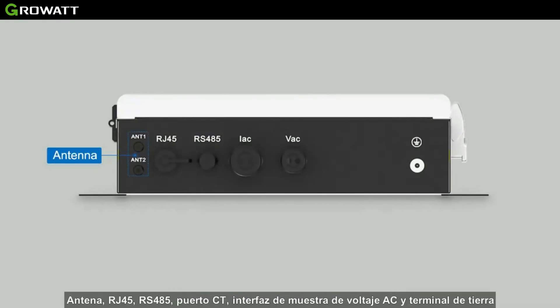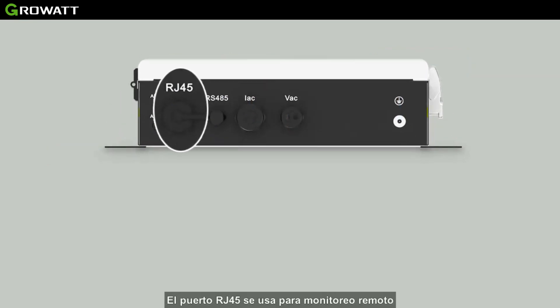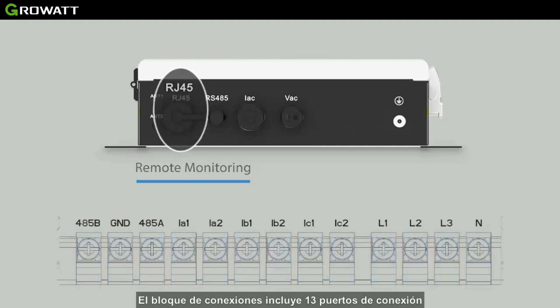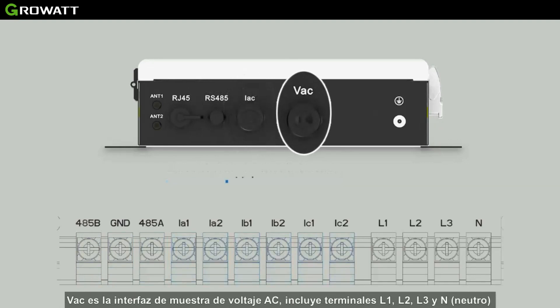With these items, the Smart Energy Manager has three main functions. The wiring terminal block terminals from left to right are: antenna, RJ45, RS485, CT port, voltage sampling interface, and ground terminal. The RJ45 port is used for remote monitoring. The terminal block includes 13 wiring ports. The RS485 communication port includes 485A, GND, and 485B. The IAC current transformer interface has three pairs of ports. The Vac voltage sampling interface includes L1, L2, L3, and N ports.